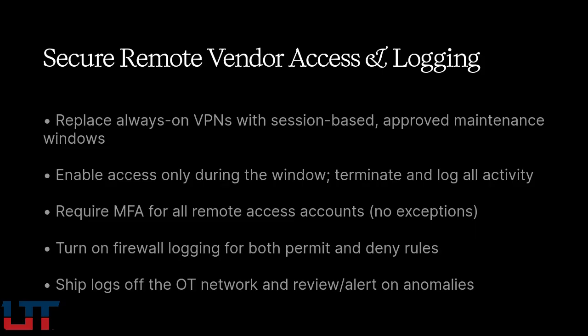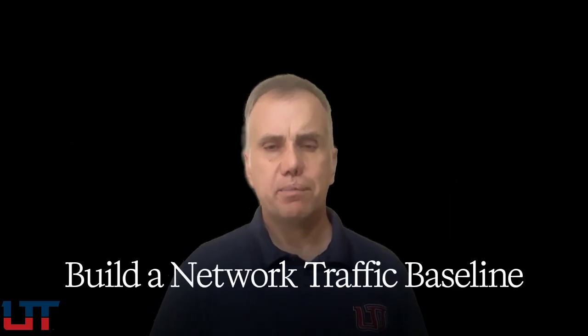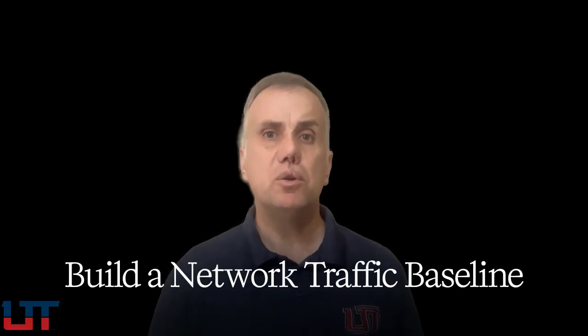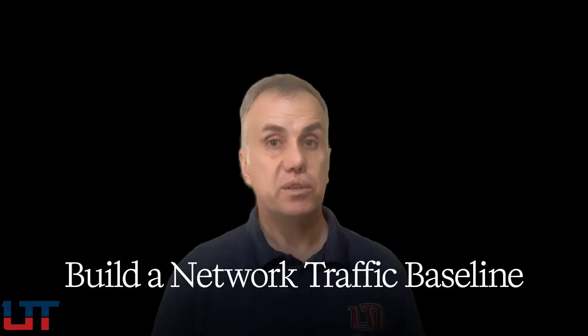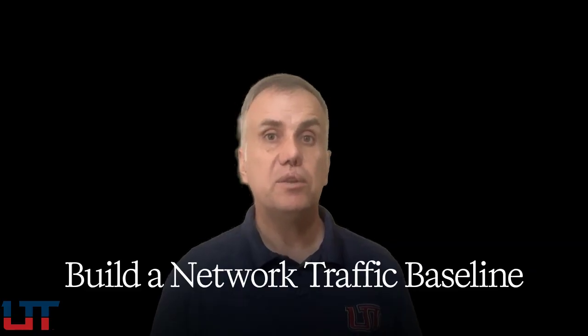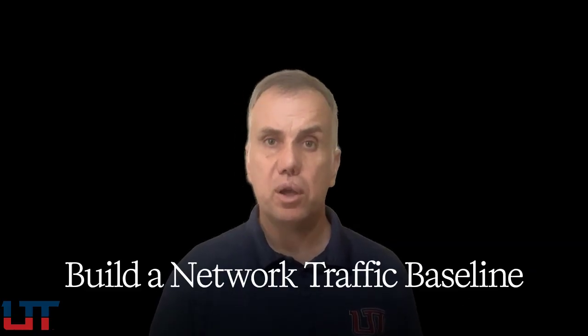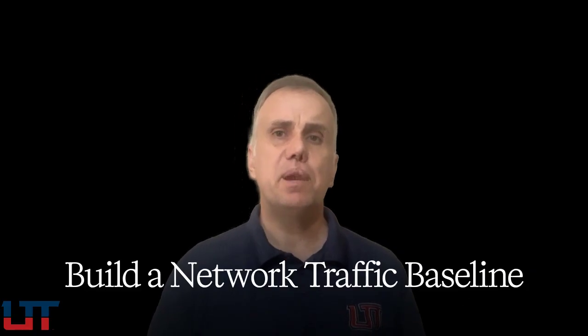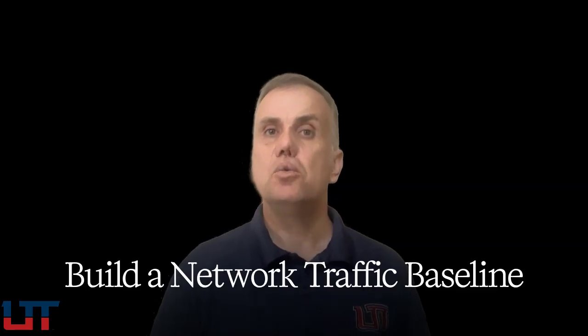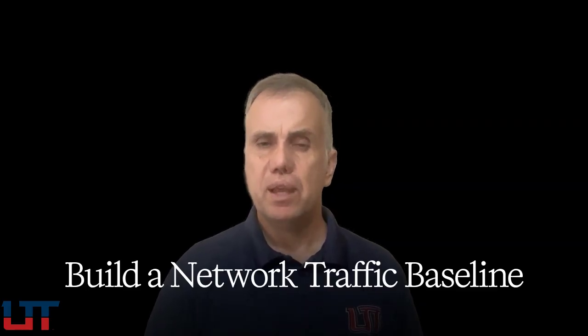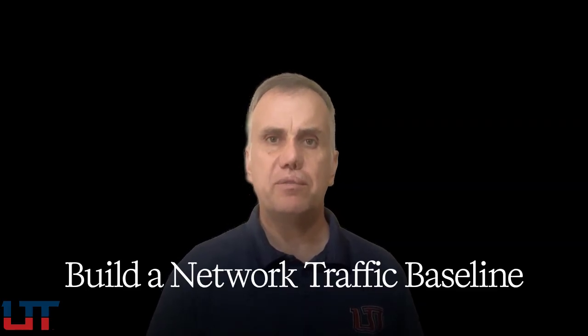Build a network traffic baseline. Document what normal OT communication looks like, which devices communicate with which other devices, and on what protocols, and at what times. This baseline is the reference against which anomalies are measured. A passive OT monitoring platform automates this and provides continuous alerting when the baseline changes.